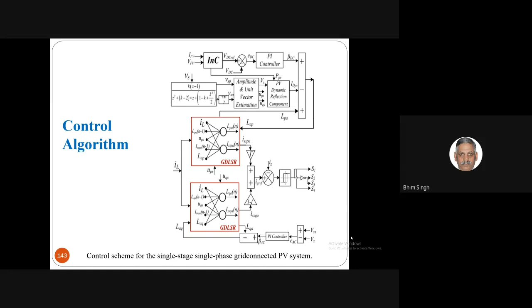In this algorithm we perform MPPT of the solar since it's a single-stage system—the same inverter has to do MPPT too, because we virtually control the DC link voltage to correspond to the MPPT voltage.